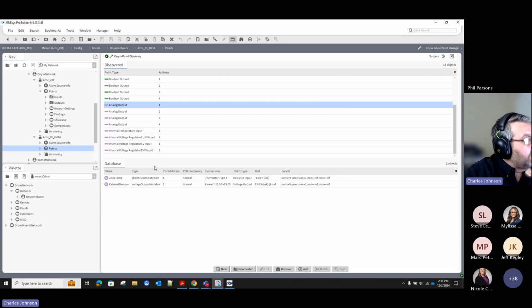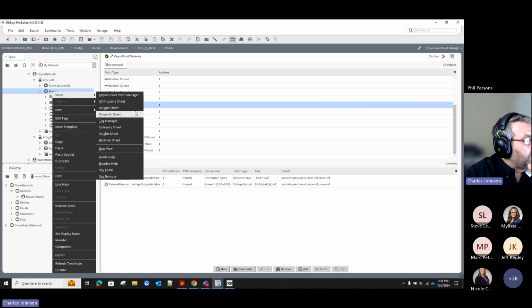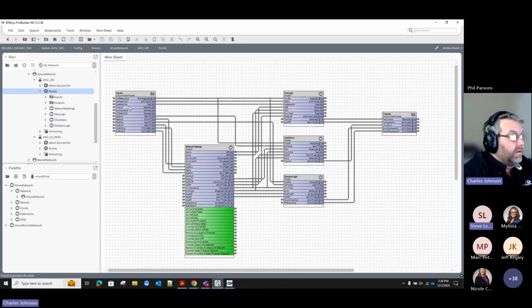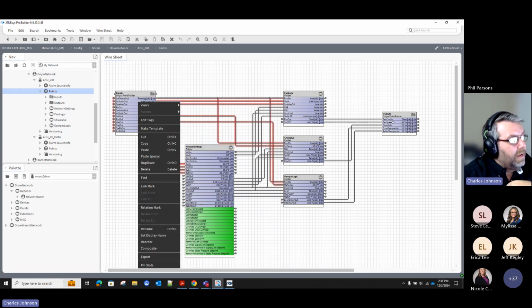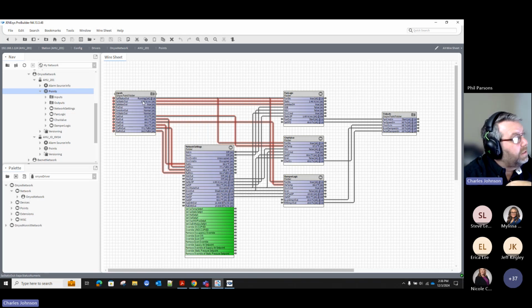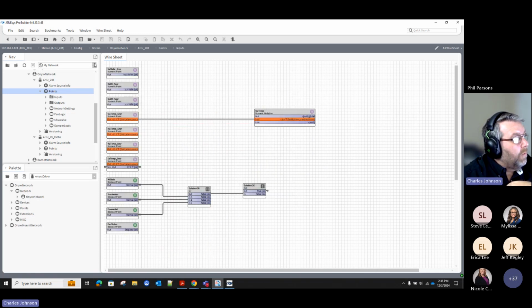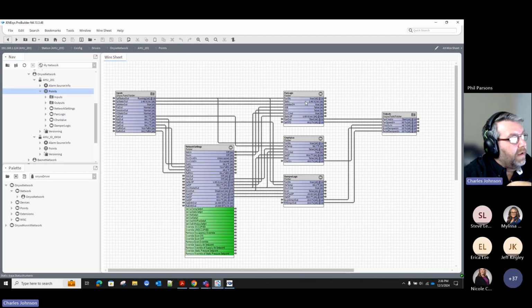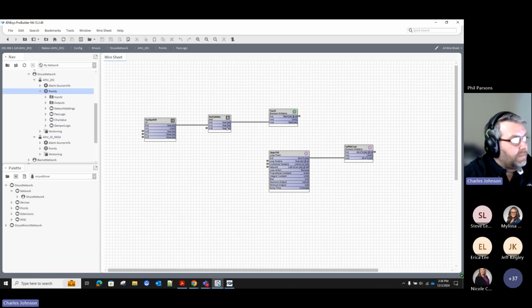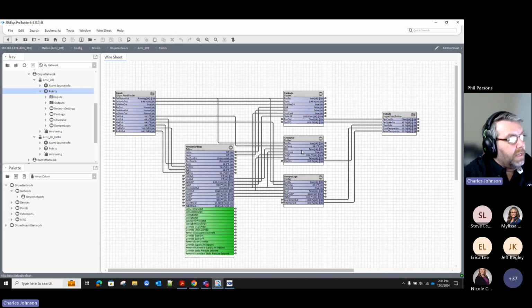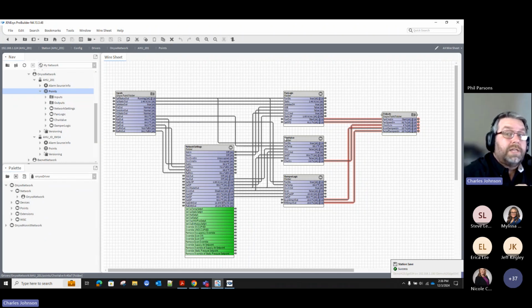Once we've set that up, we can actually create our logic much like we would in any Niagara device. I have a bunch of folders here — I like to separate my inputs and outputs, inputs to the left, outputs to the right. If I go into the wire sheet of each, we can see I have some logic here for my safeties, my fan logic, and this is all just very simple logic. Same thing here for chill water valve, and my outputs here. So I like to keep everything folderized as much as possible for organizational purposes, but you can certainly put as much logic on a wire sheet as you'd like.